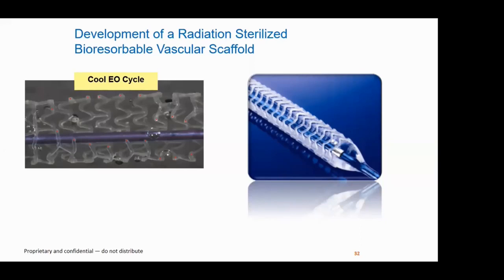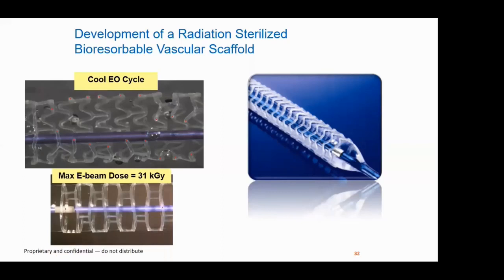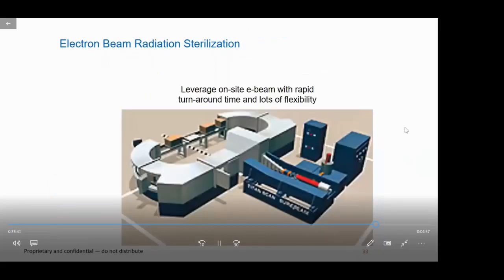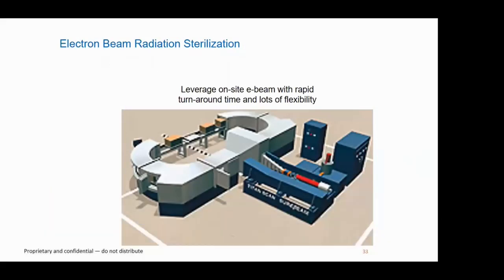That was true of other issues with alternative gases that we explored. But as we did e-beam, we were getting a reduction of molecular weight of the scaffold, though we could manage that, and we fought for every kilogray we could squeeze out of the process. We ended up with a max dose of 31 kilogray that was compatible with both the drug—the drug loss from radiation sterilization was at an acceptable level—and the performance of the scaffold was acceptable at 31 kilogray. As I mentioned, we leveraged an on-site e-beam, which was nice because we had rapid turnaround time for development and a lot of flexibility—when we were concerned about temperature spikes, we could cool down product before we processed it. That was very helpful in development.